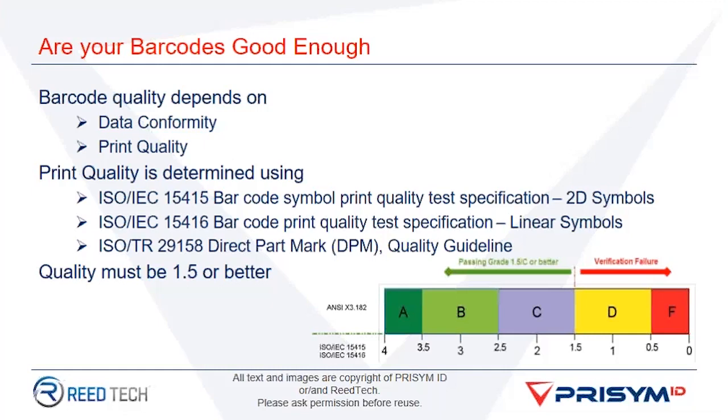We've seen this verification done at different parts of the design, approval and production process by some of our customers. Some of them verify the quality as part of the design and approval process, then ensure that their printers produce an equivalent quality by following a regular maintenance and calibration plan for each of those printers, very similar to how you would other devices on your production lines.